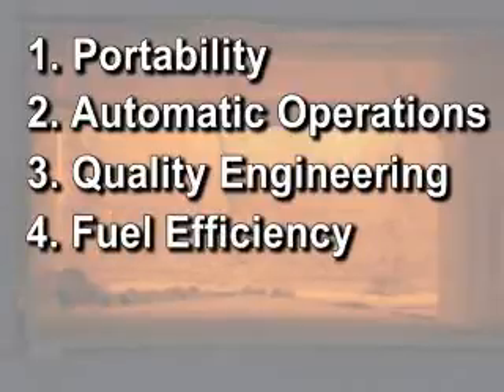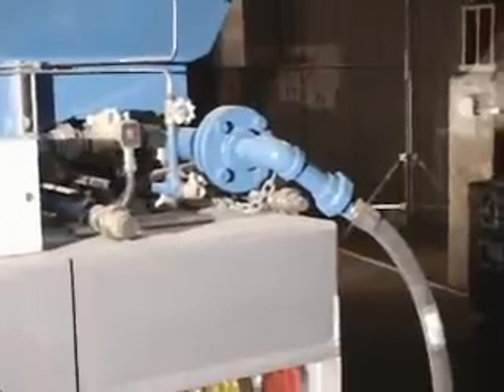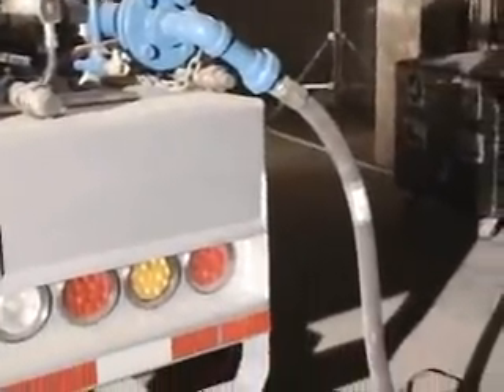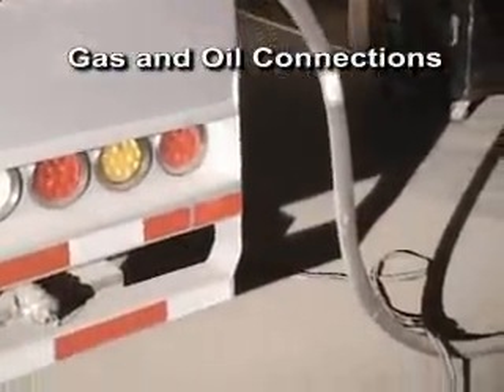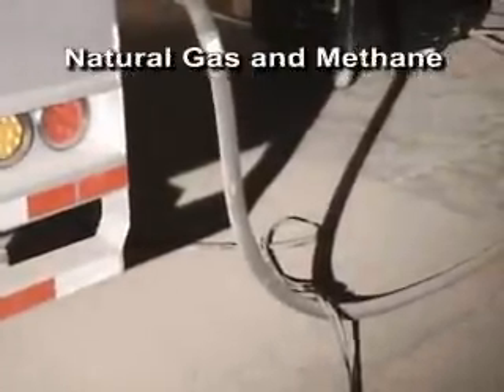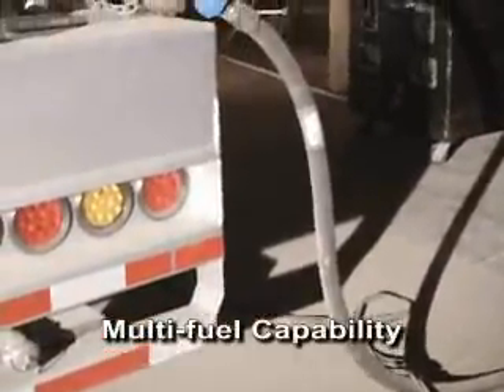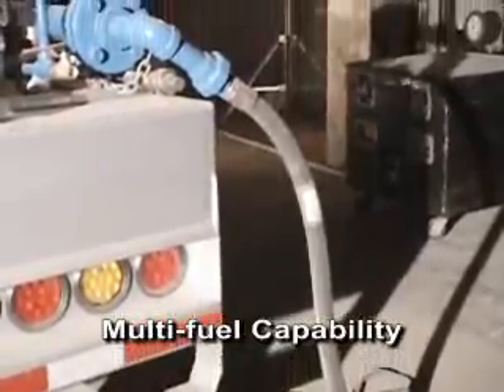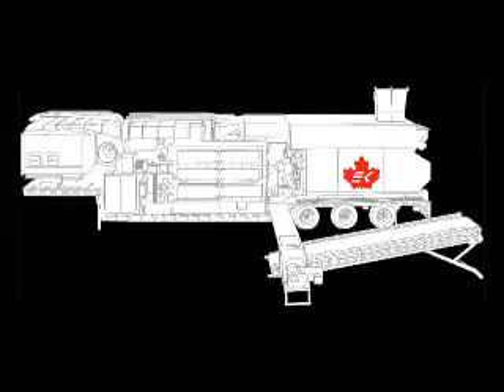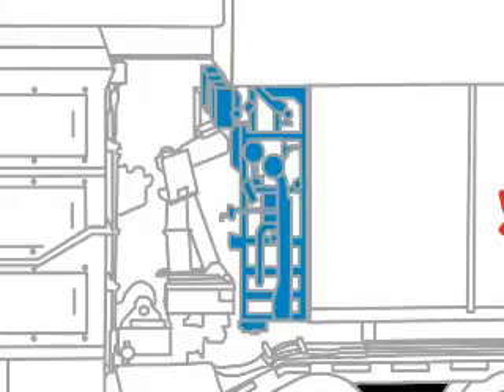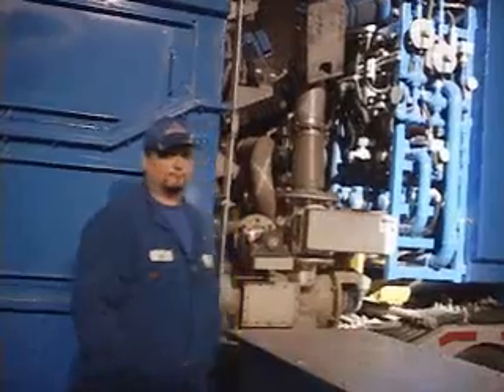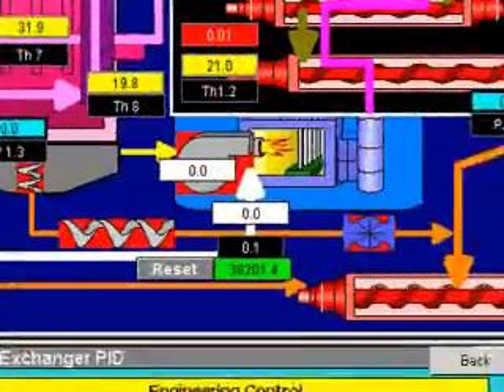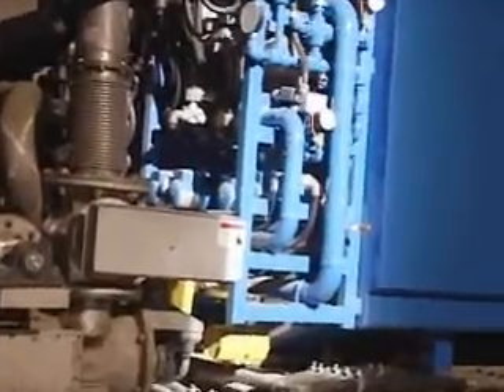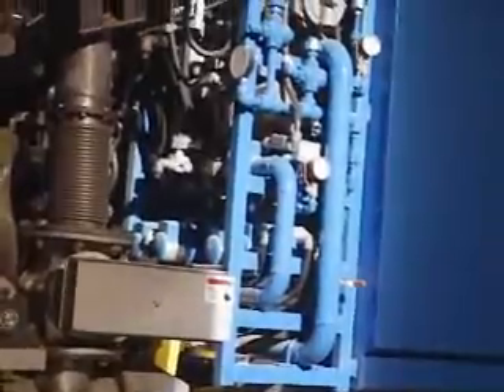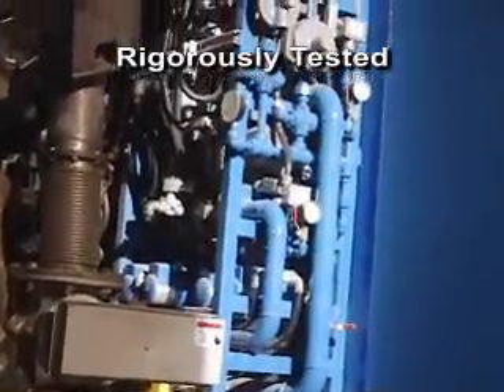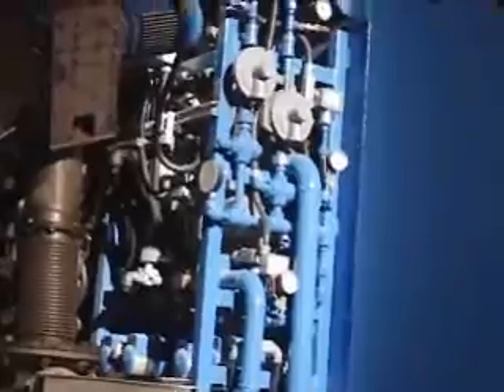Fuel efficiency. The fuel connections are located at the back of the machine with a separate connection for both gas and oil. The gas connection can be used for natural gas or even methane. Multi-fuel capability helps to minimize varying fuel and operating costs. All the fuel line controls are mounted in a common area in the center of the trailer and relay fuel consumption data back to the control house. Each KM4 has the piping, regulators, valves, and meters all custom installed and rigorously tested for safety and performance.